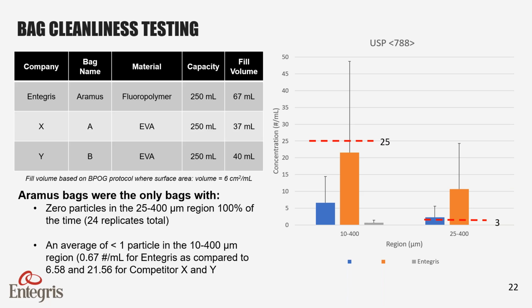The chart on the left shows the 10 to 400 micron range where the limit is 25. Entegris is very far below the competitive products in that space. As you can see, the standard deviations of some of those products would take them above the limit for USP 788, which means that overall Entegris assemblies have much lower particulates than their EVA competitors.